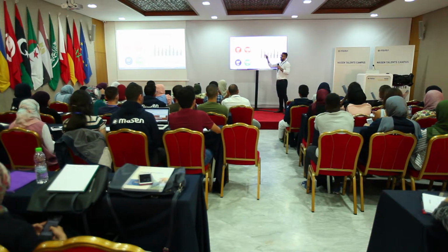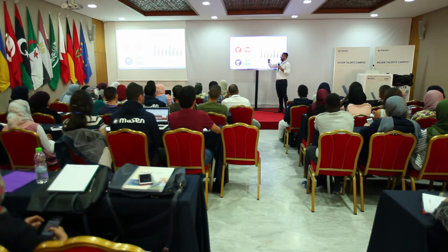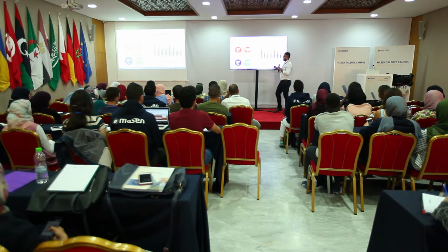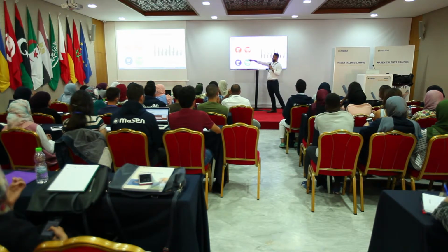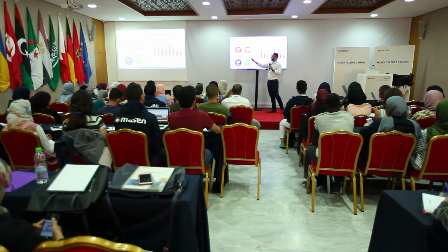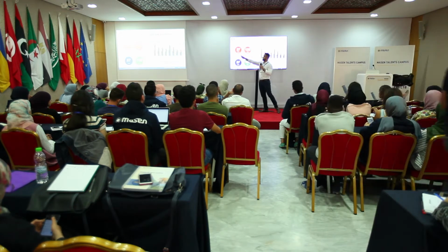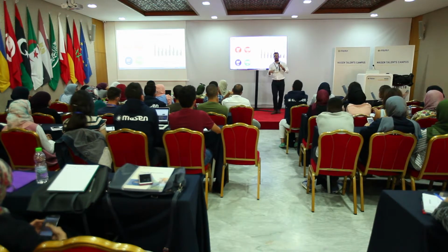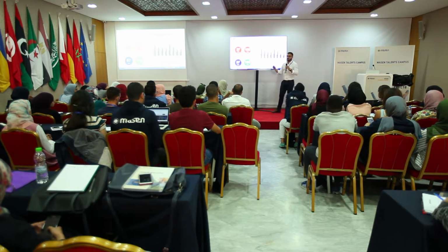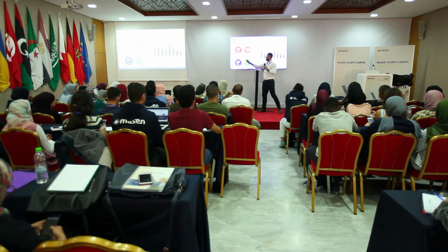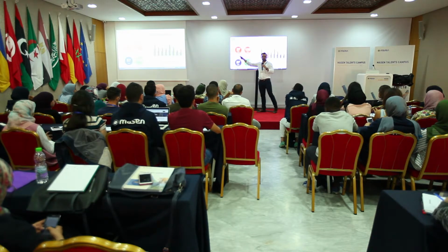The difference between trough and tower is that in towers, it's direct. The molten salt is the same fluid that is the heat transfer fluid, so we don't need these heat exchangers. In trough, it's indirect. The heat transfer fluid, the one getting hot with solar energy, is oil, and the storage is salt. So there is this indirect step. That's the only difference there.